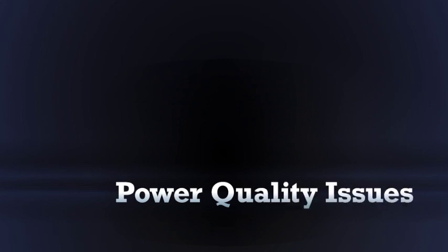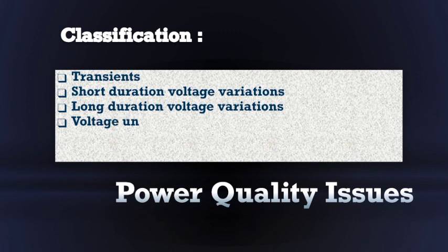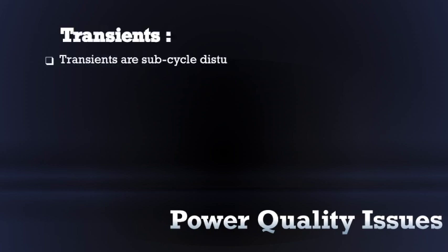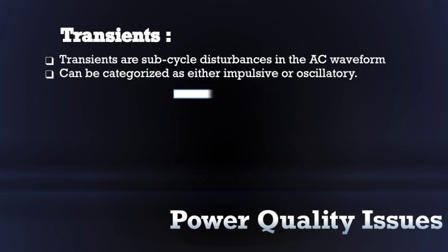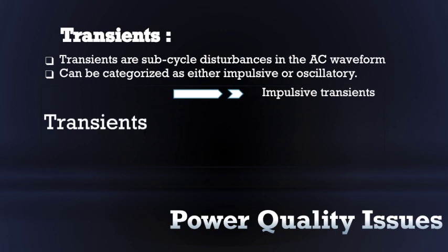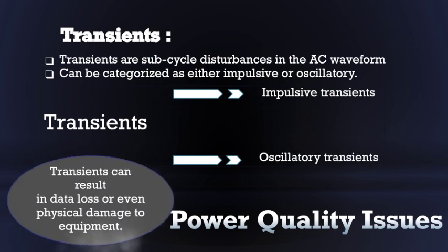Now we will move on to various power quality issues. Power quality issues can be classified into 5 categories: transients, short duration voltage variations, long duration voltage variations, voltage unbalance, and waveform distortion. First we will look into transients. Transients are subcycle disturbances in the AC waveform and can be categorized as either impulsive or oscillatory. Transients are possibly the most damaging type of voltage disturbance.